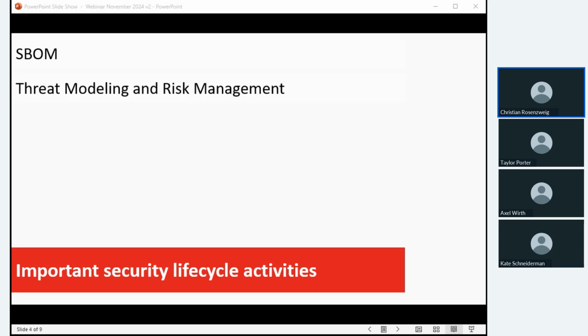So the result of this security risk analysis must be consolidated with the safety risk analysis in order to find impacts of security issues on the health of humans. So there's a link between the security risk analysis based on threat modeling and the corresponding ISO 14971 risk management process. And for third-party components, we cannot do a proper threat modeling, as third-party components are black boxes for us. So we need another risk analysis method, and this is exactly what we said: the SBOM must be used to identify known vulnerabilities by monitoring public vulnerability databases.